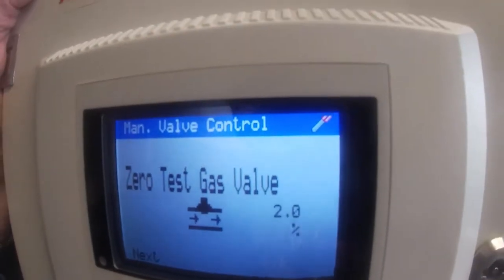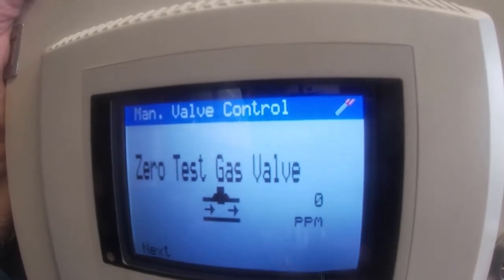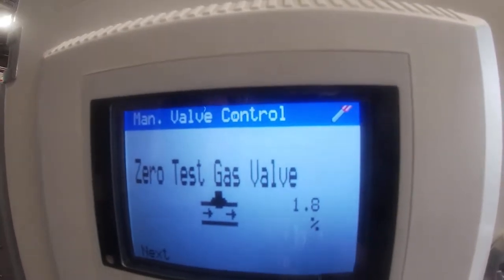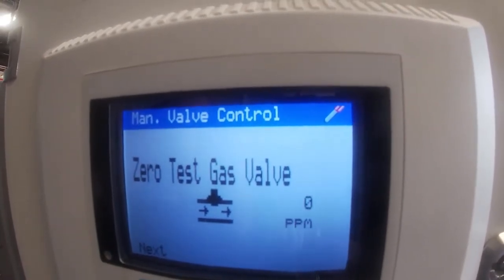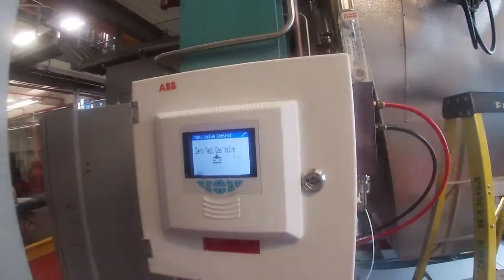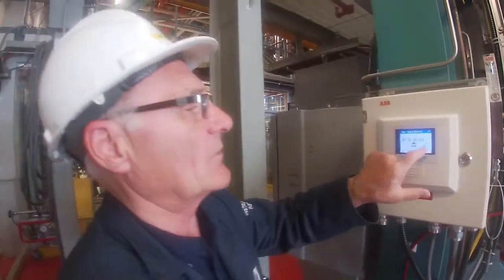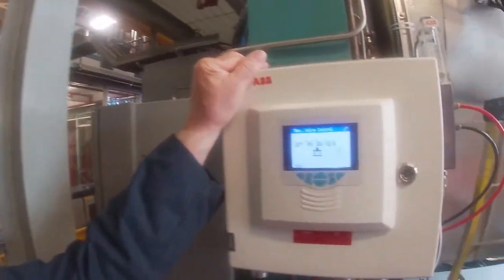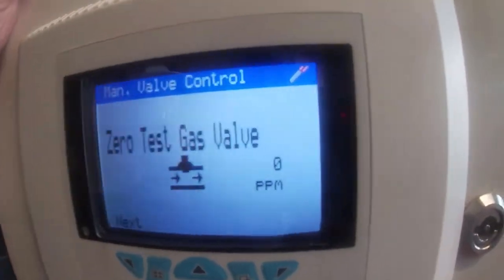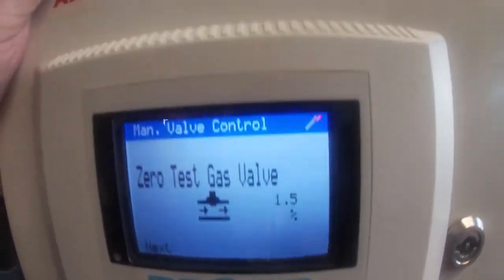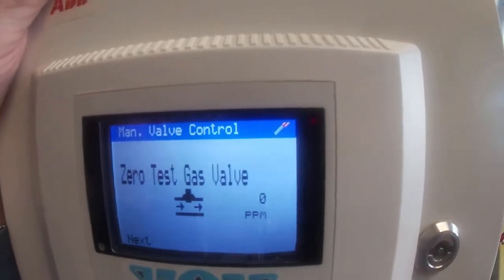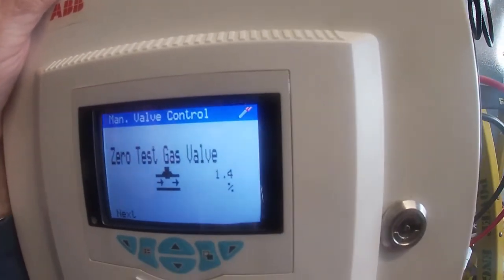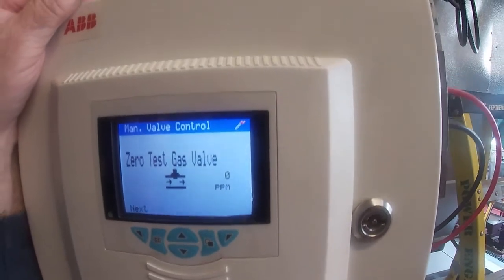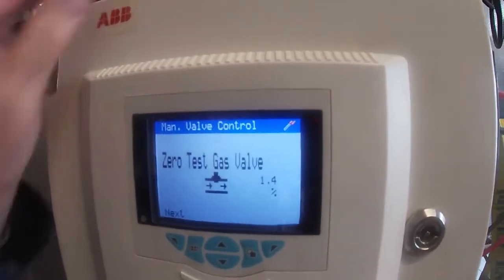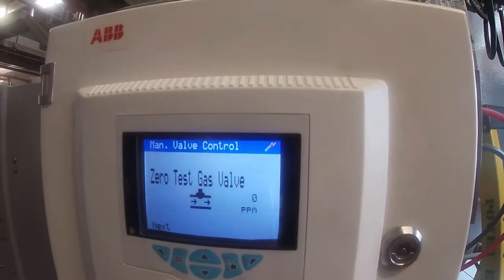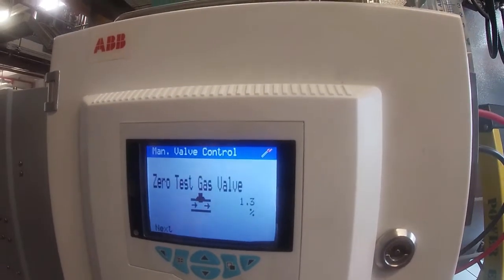It should go down to around 1%, because we say we're injecting 1.01%. You're allowed plus or minus 0.1 on here. Right now it's saying we're down to 1.5, which suggests to me that it's out of calibration a little bit. It hasn't been calibrated for 6 months, actually longer than that, so not surprising. It's down at 1.4% instead of the 1.01%.